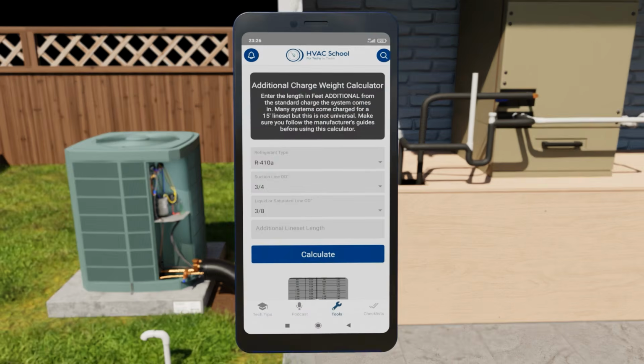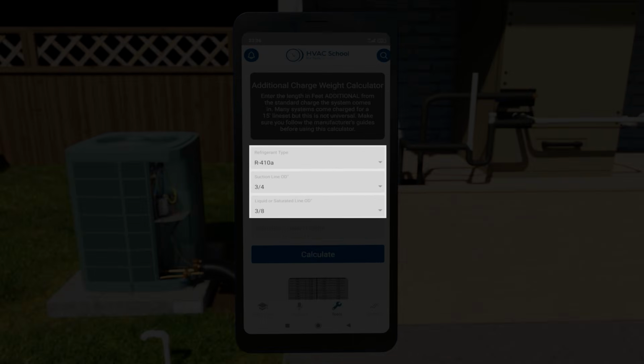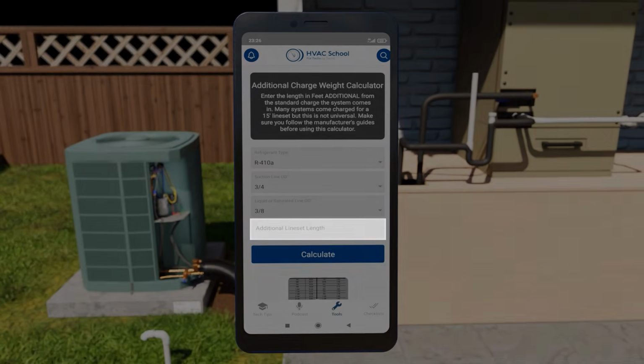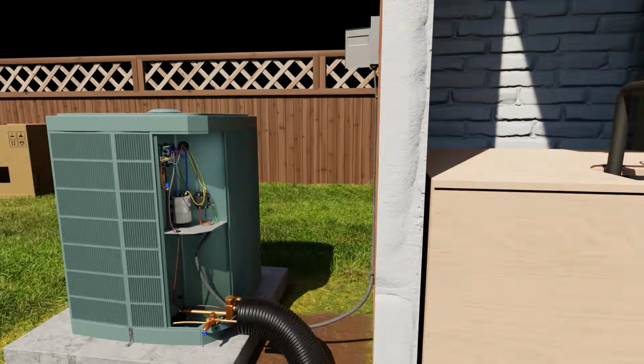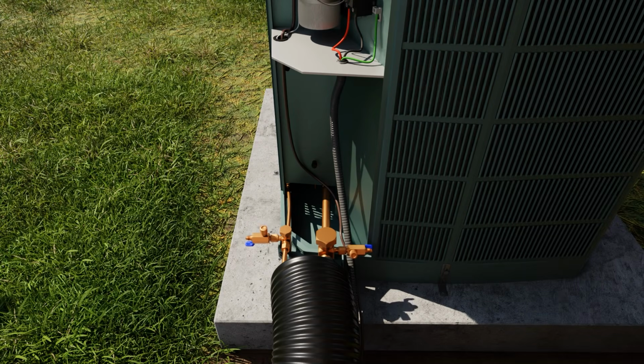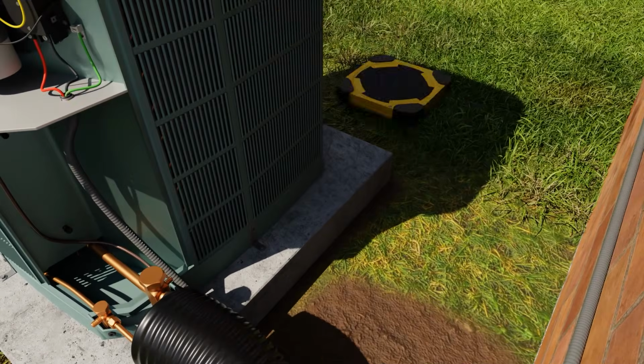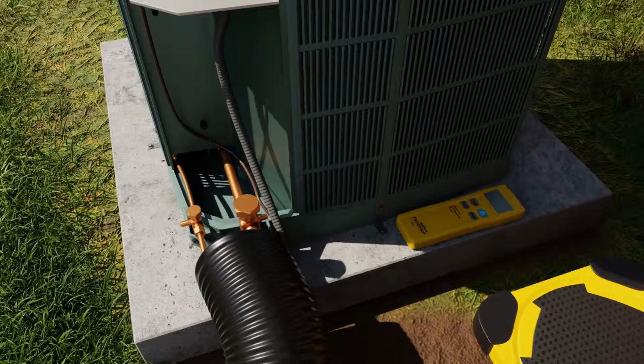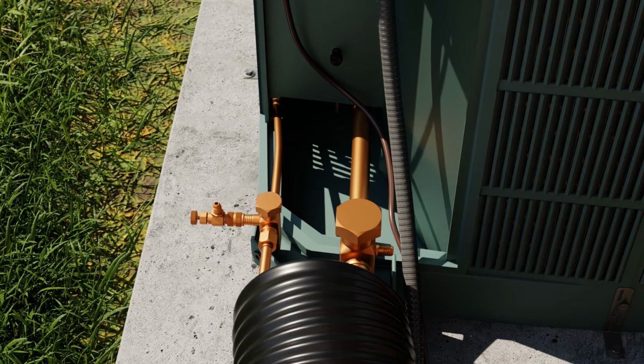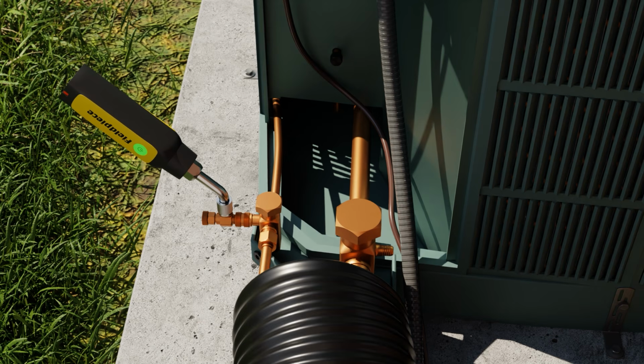We also have a charging calculator for different line lengths on the HVAC School mobile app, because you use line lengths to figure out how much additional charge to weigh into the system. In addition to that, you still monitor your pressure, subcooling, superheat, and follow your manufacturer's literature for charging. Get out the scale and place your refrigerant charging tank onto the scale. Here, we're showing how to use a core depressor to control the flow of refrigerant.